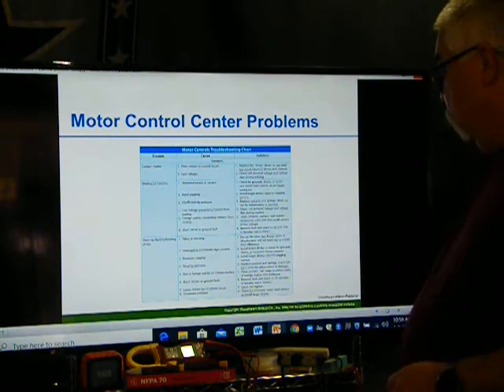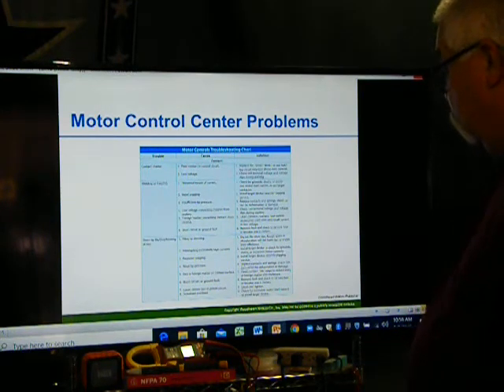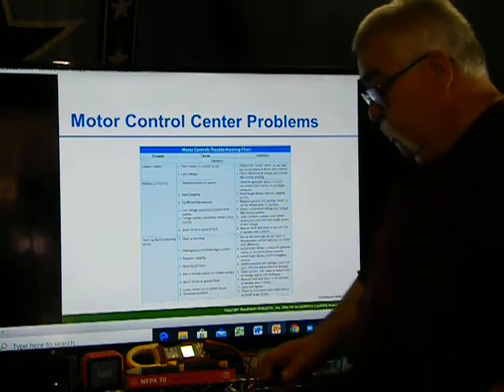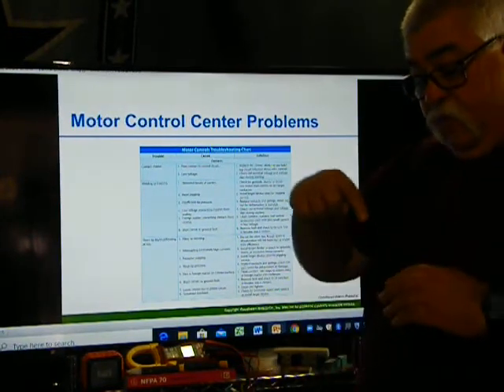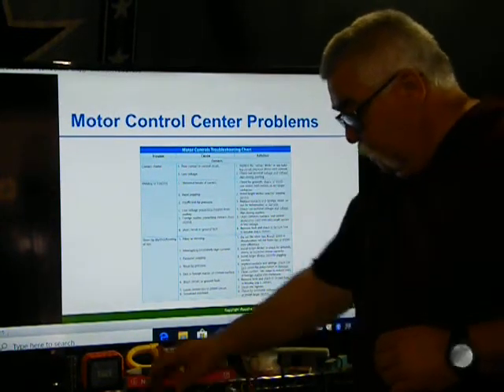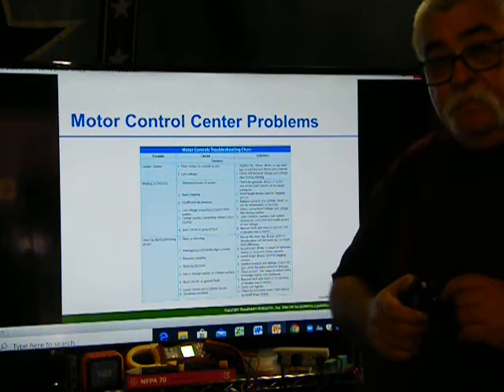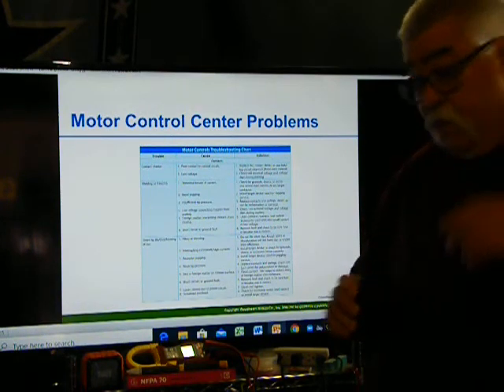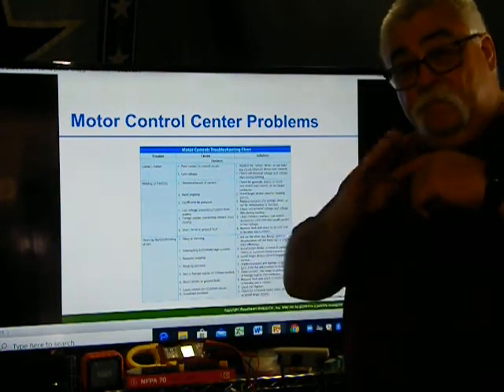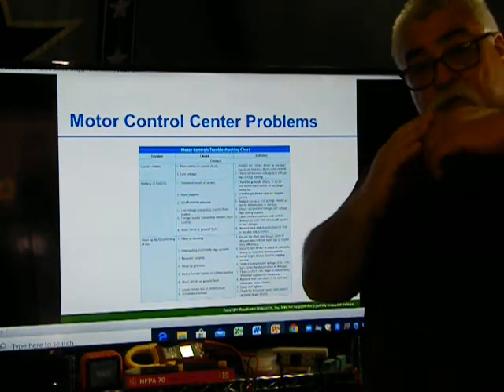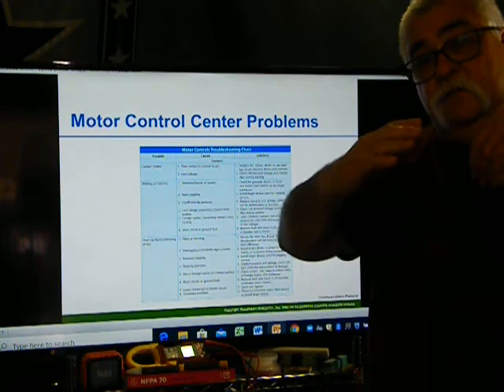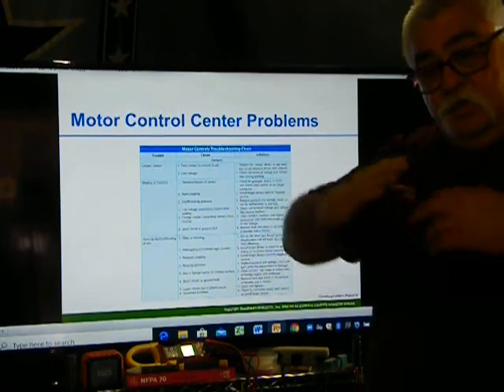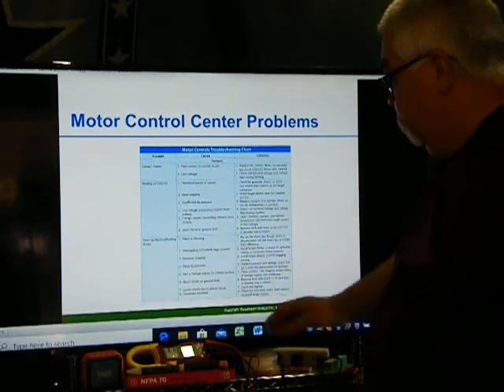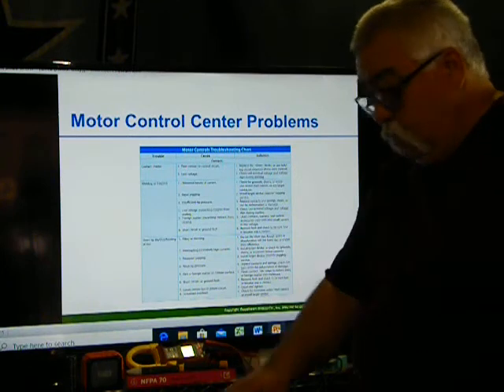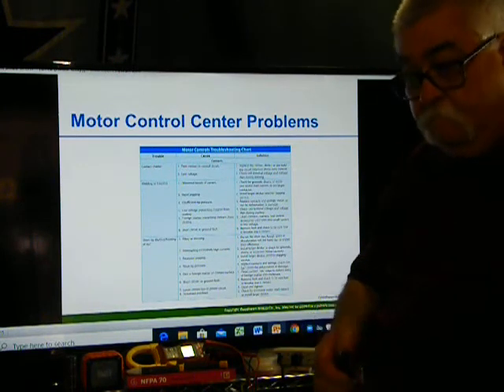Short circuit or ground fault, remove the faults. Loose connection in the power circuits sustains overload. So if you have a wire and you don't tighten the screw down, you just stuck the wire. It's making contact, but it's arcing because it's making contact, breaking contact, making contact, breaking contact. Why? Because it gets hot and expands and contracts, expands and contracts. So it causes this arcing. So with a loose connection, it doesn't give you the proper voltage.